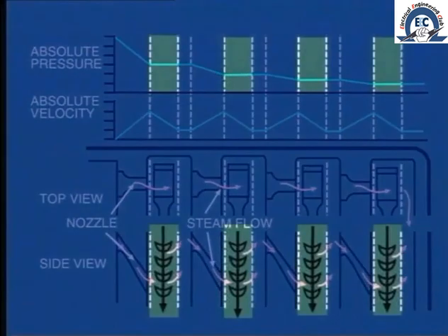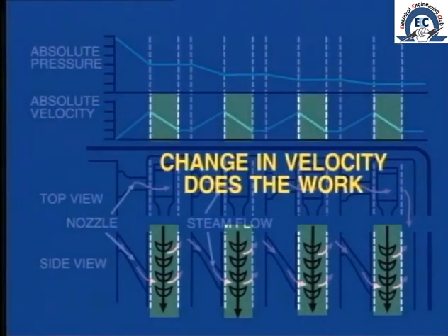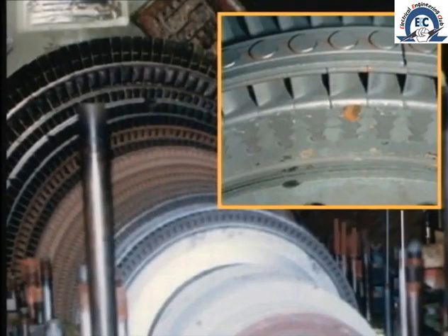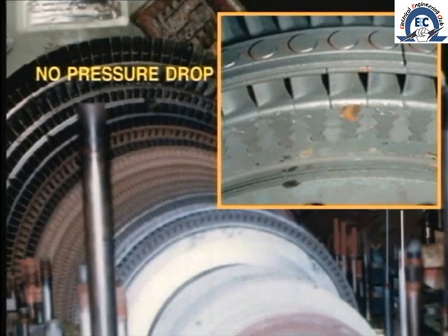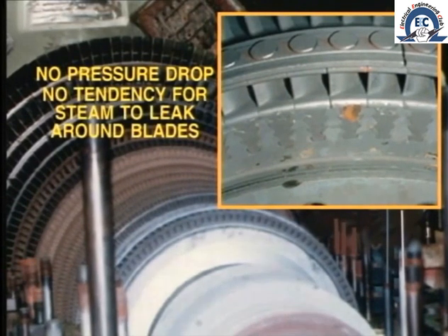But look at what happens here to the pressure as the steam passes through the moving blades. It does not decrease, neither does it increase. In fact, the pressure across the moving blades remains the same. It is the change in velocity which actually does the work and provides the energy to drive the turbine. This feature of impulse blading — that is, constant pressure across the moving stage — brings about a certain constructional advantage. As there is no pressure drop, there is no tendency for steam to leak around the outside circumference of the blades. Because of this feature, we will inevitably find that impulse blading is used in the high-pressure stages of the turbine.